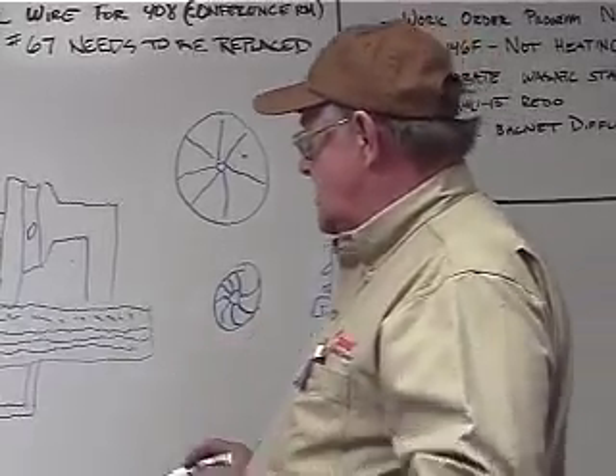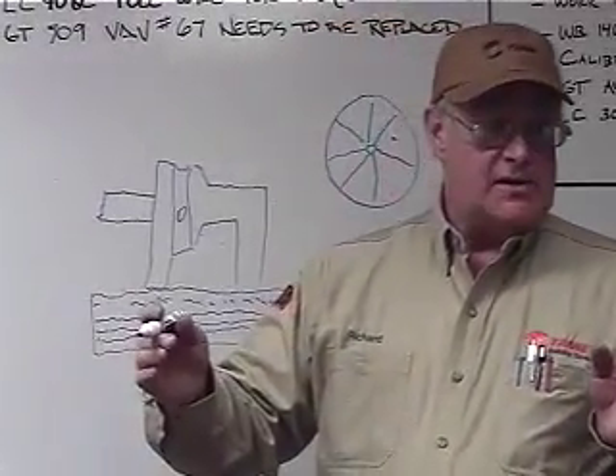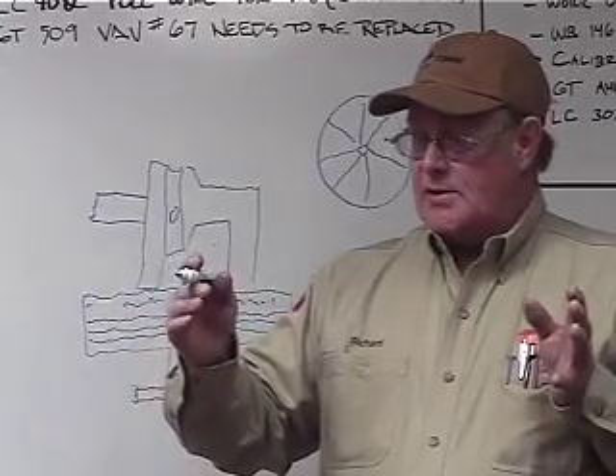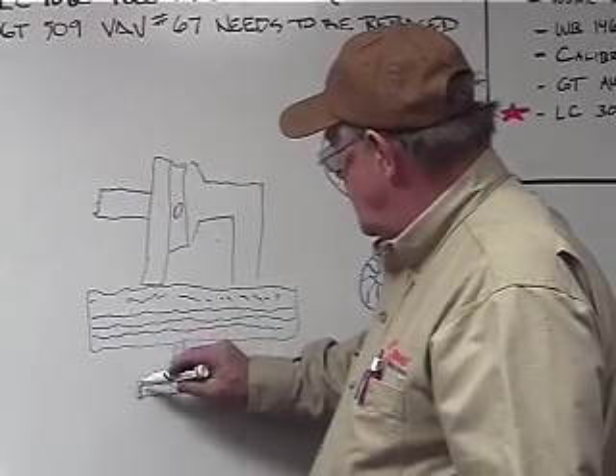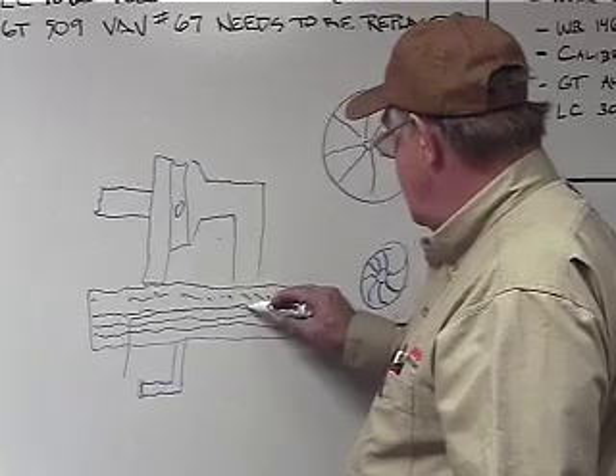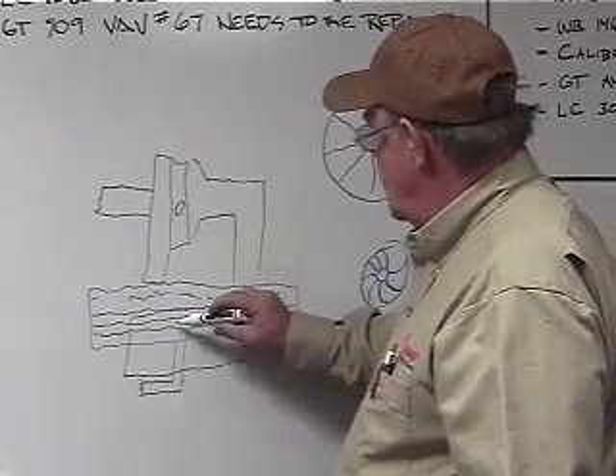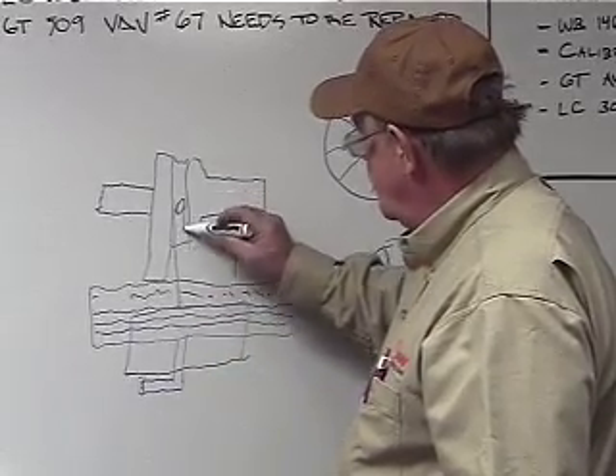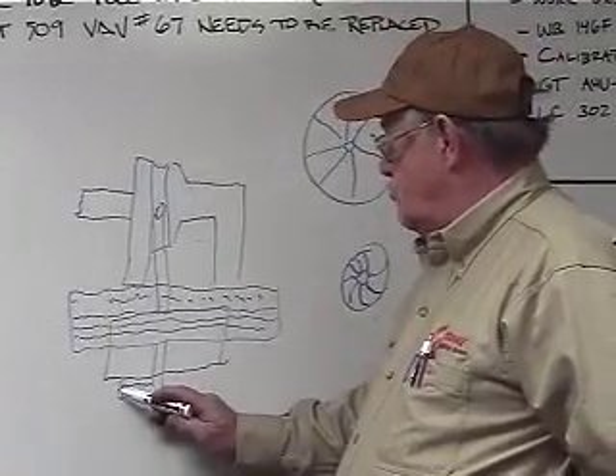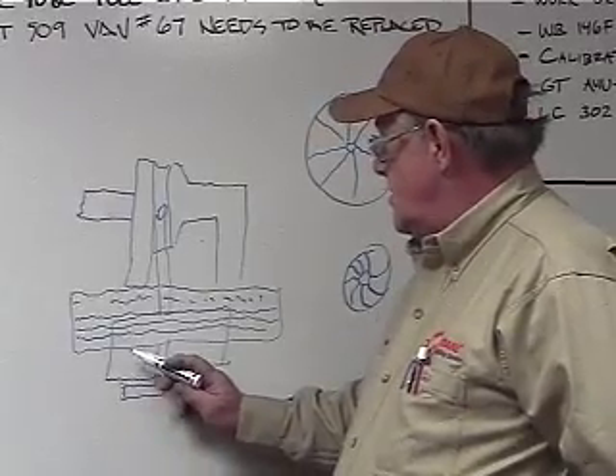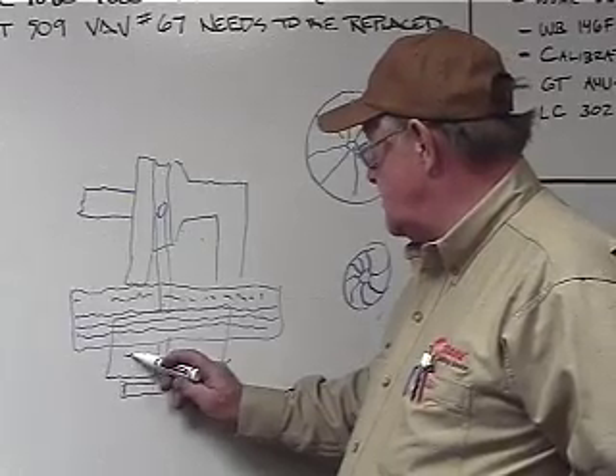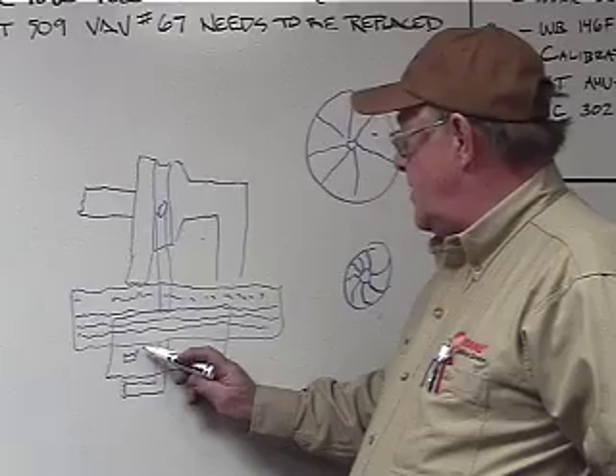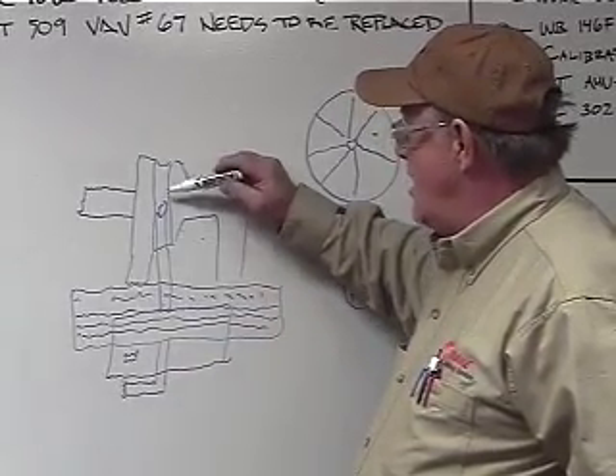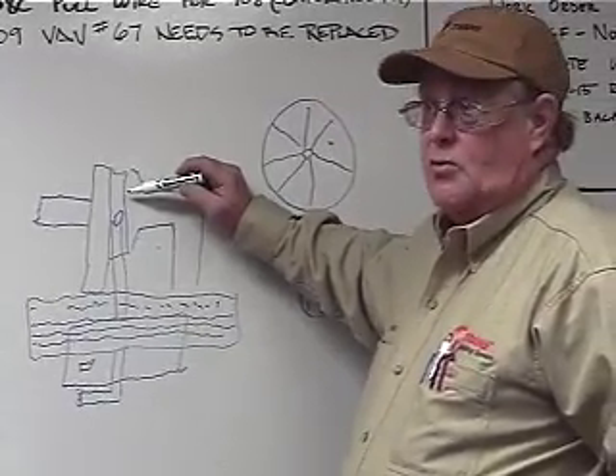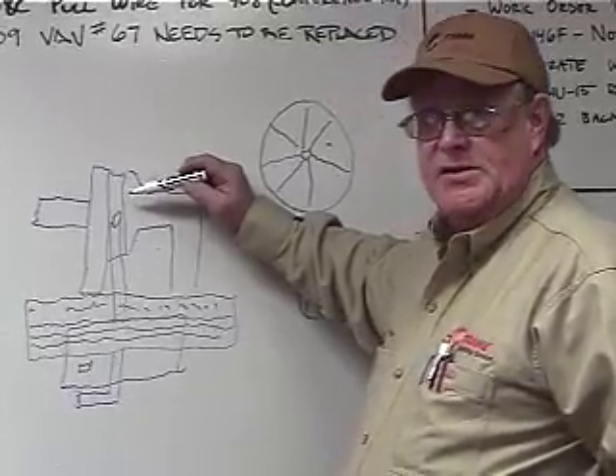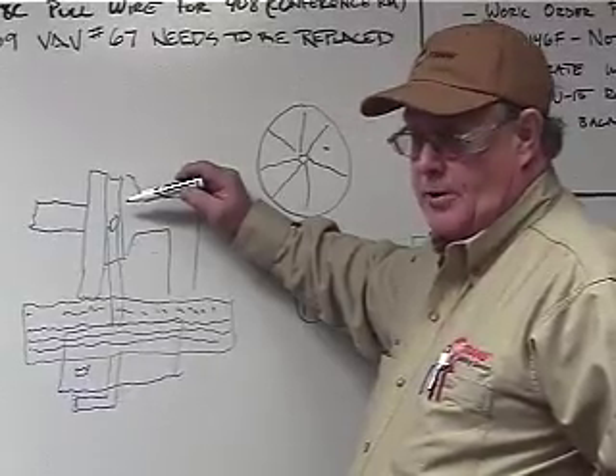It starts breaking it up, and it ties into what we call an economizer, which is that black thing on the side of your chiller, and it's covered with insulation, and it's got a leg. So the economizer is going to come up like this on your chiller, and you're going to see a tube that comes up to this hole. As your liquid refrigerant starts to break up and become a vapor again, it goes through the economizer, and there's another orifice plate up in here that starts breaking it up into a vapor, and the vapor that's actually been broken up will go back into your second stage volute, which they call an economizer, so that it doesn't have to send all the gas and refrigerant back down into your evaporator.